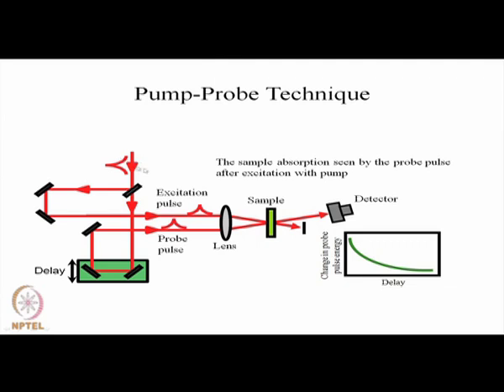Okay. But if it is faster than nanosecond, then electronics cannot do. It has got some basic limitation. So, therefore, you have to take the help of light to generate your time axis. Okay. So you see that this is your excitation pulse. Okay, it is divided into two. Maybe it is a 50% beam splitter. Okay, then this is directed this way. So, this is your excitation pulse, and another portion, maybe most of the pulse, maybe say 90%, not 50%, is directed this way, only 10% is directed this way.